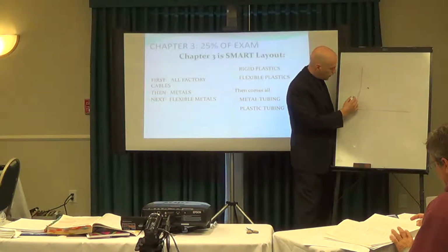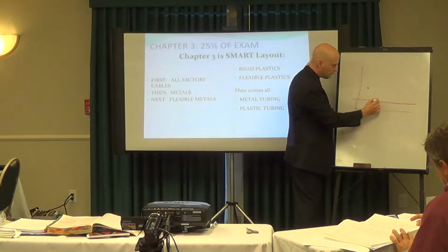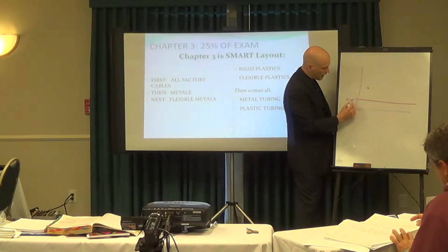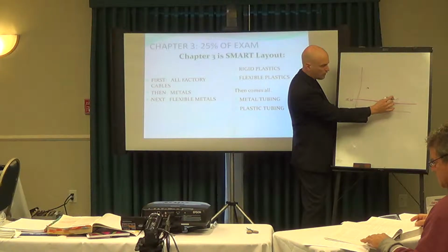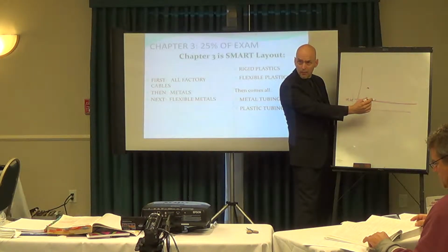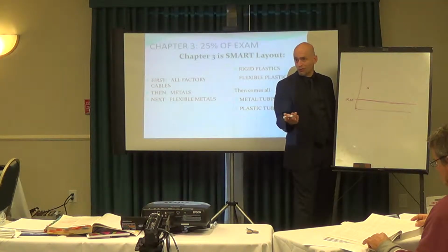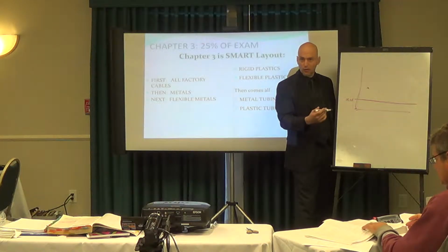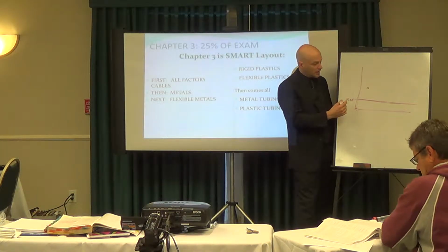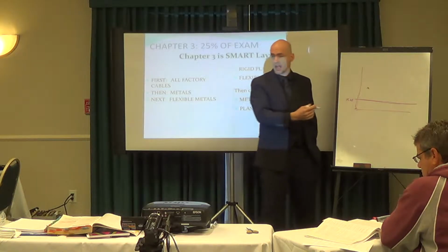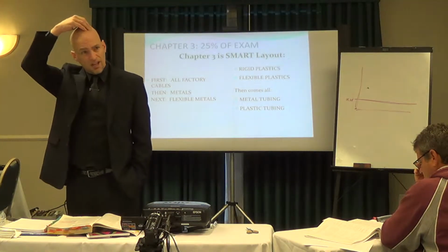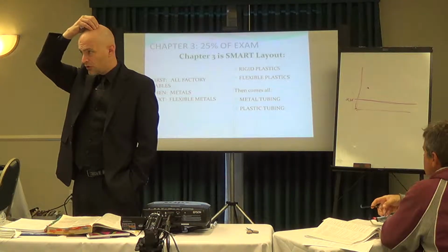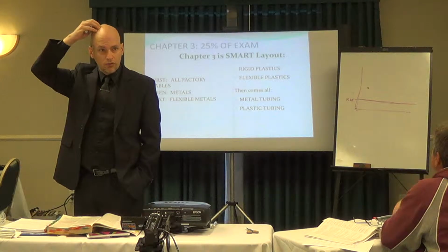So a thermal event is what that 20 amp rating is. So, 20 amps, I can run a breaker somewhere right at 19.9, or maybe right at 20 for a considerable amount of time. After about 3 hours or more, it's going to be enough heat on that conductor to probably eventually trip it. But it may happen over a long span of time. And if you ever put on a breaker and it took a second or two and then finally tripped, and it was kind of a soft trip, have you ever had that happen to you? That's a thermal protection, okay?